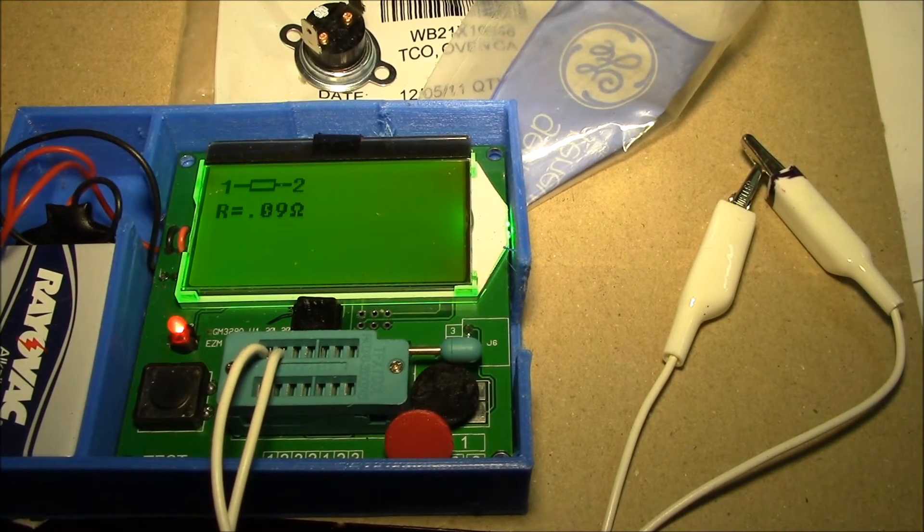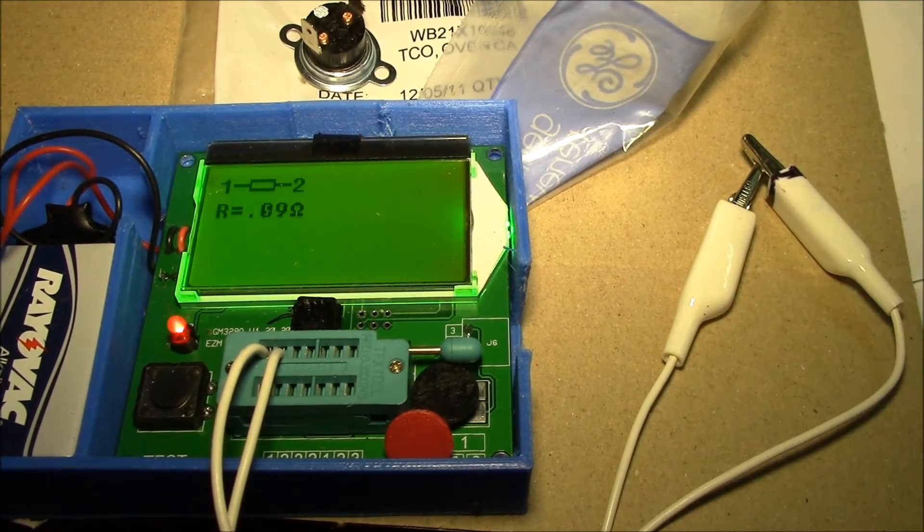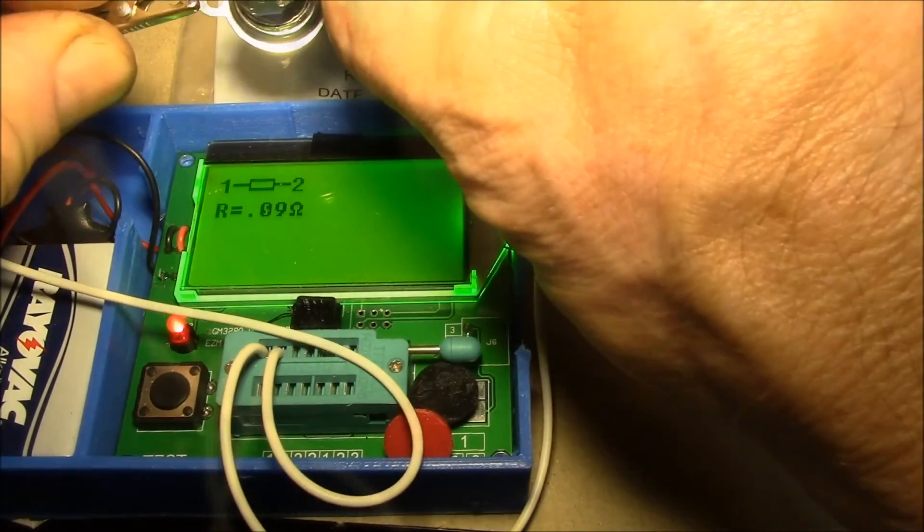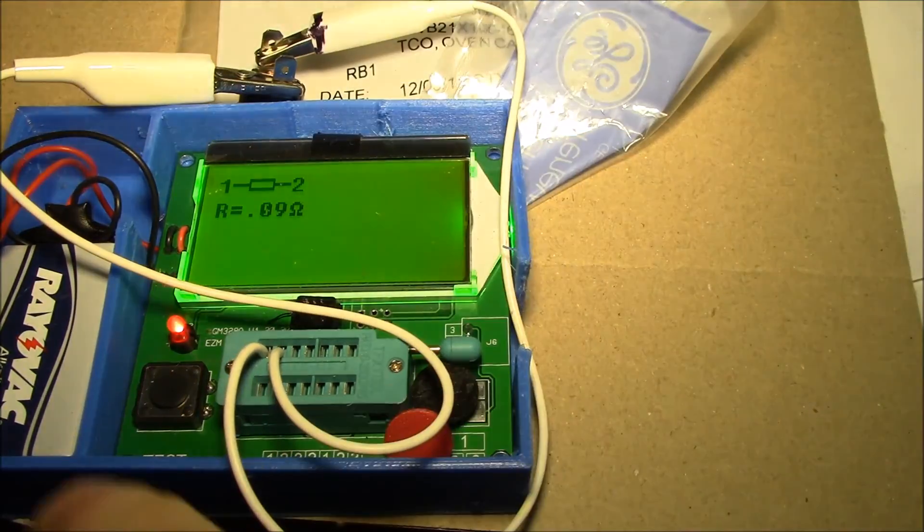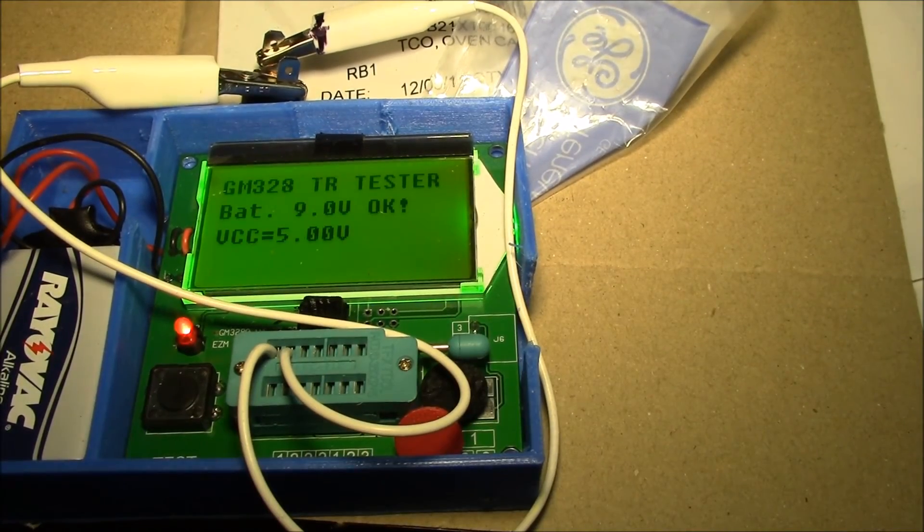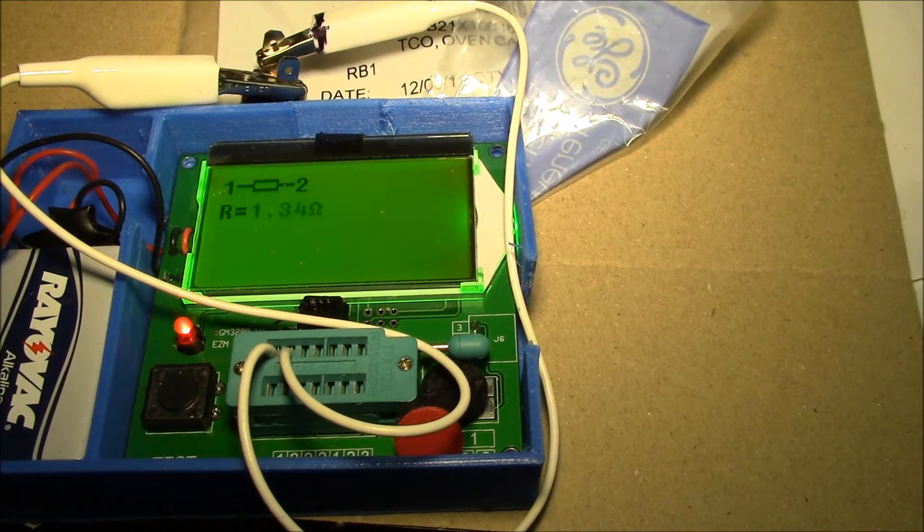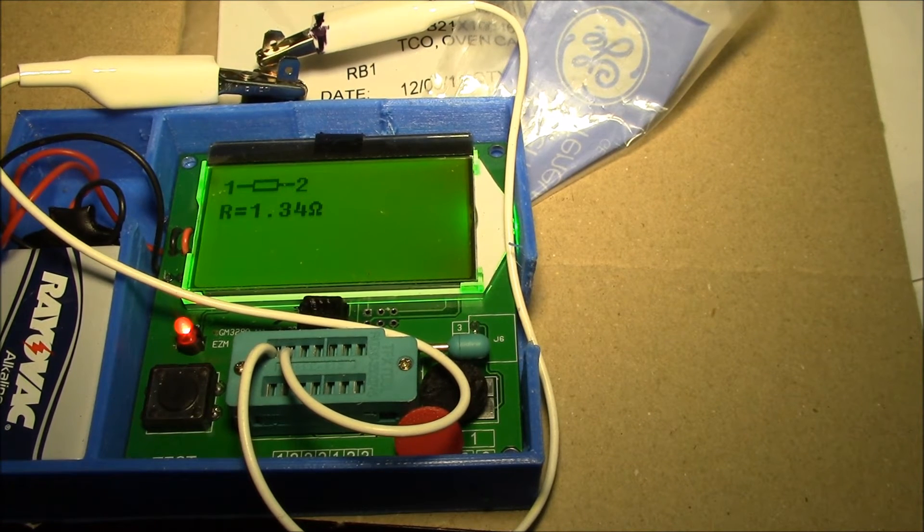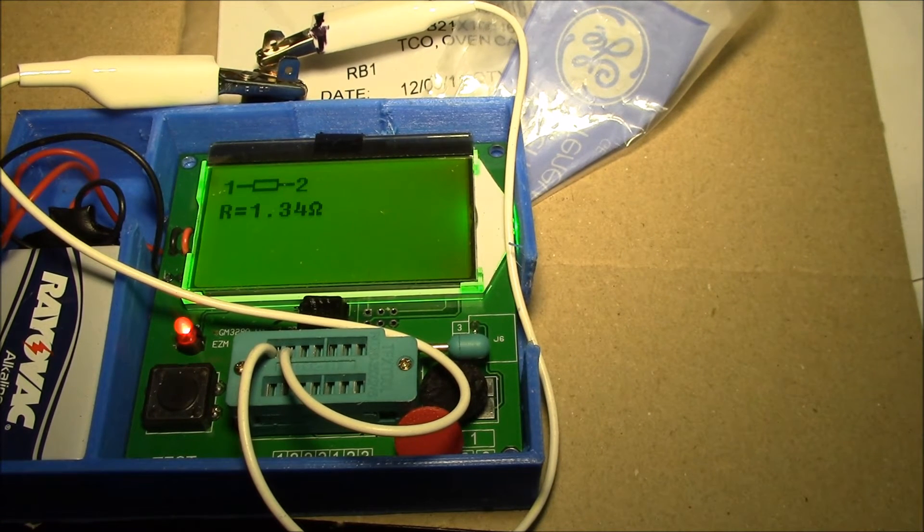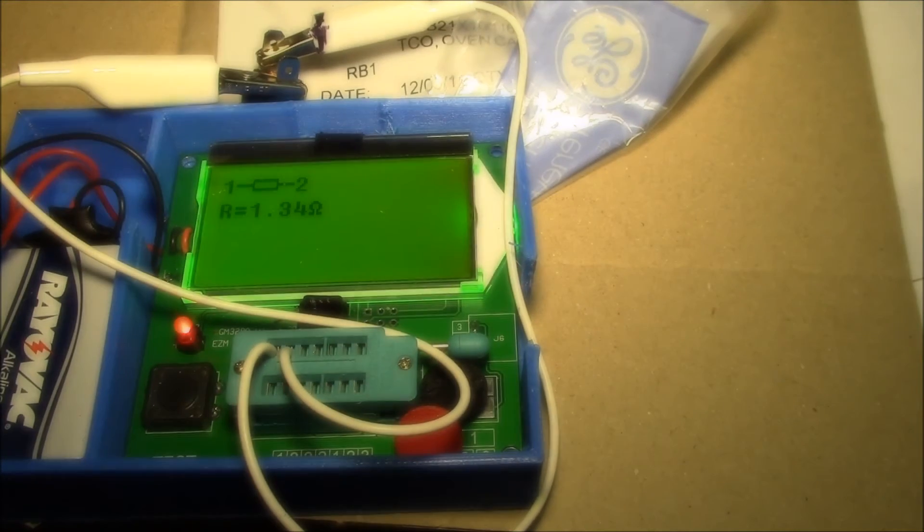Let's try a second meter just to get a second reading. It says the resistor 0.09 ohms, then let's clip on to the TCO thermal cutout and we'll retest - 1.34 ohms. That's pretty similar to the other meter.